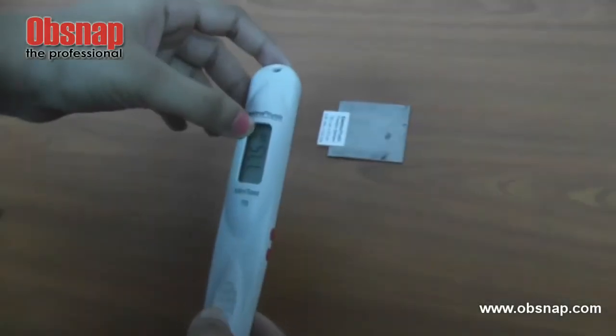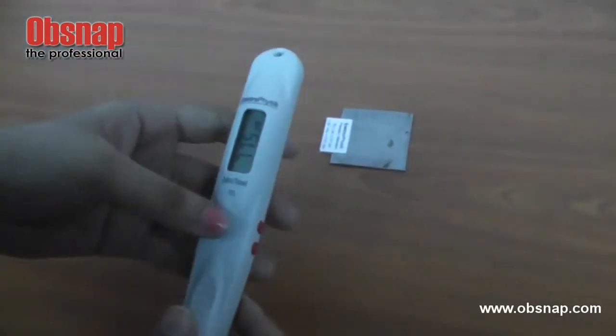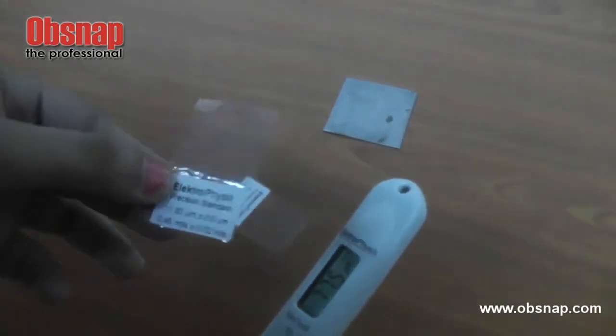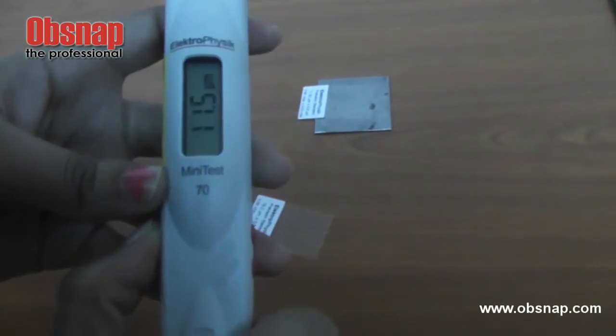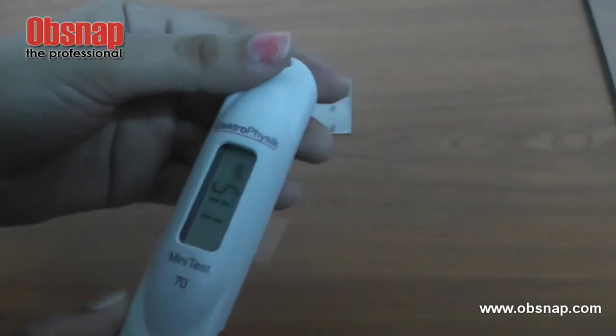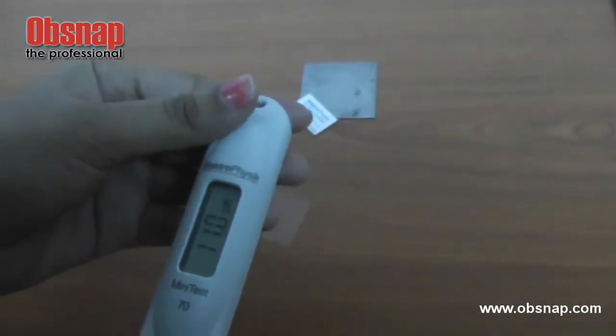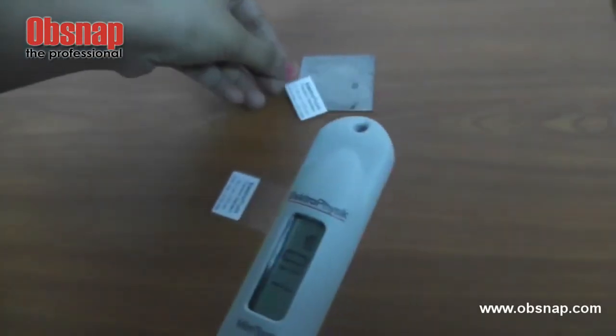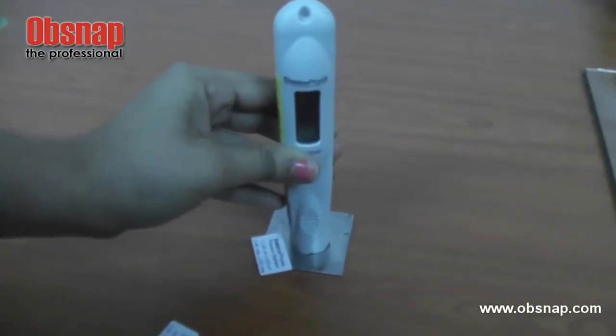If your first point calibration is changed, you have to recalibrate according to the precision standard you will be using. For example, if you are using a different precision standard, 11.32, you have to recalibrate according to the standard sample. So if it's 10.5, you can calibrate by pressing this calibrate button, adjust the reading to 11.5, which is close to the standard foil 11.32 micrometer, and then you place it on the sample.